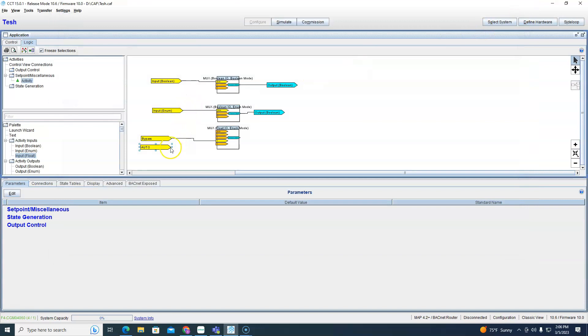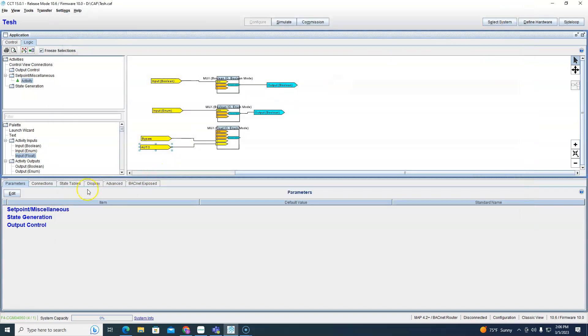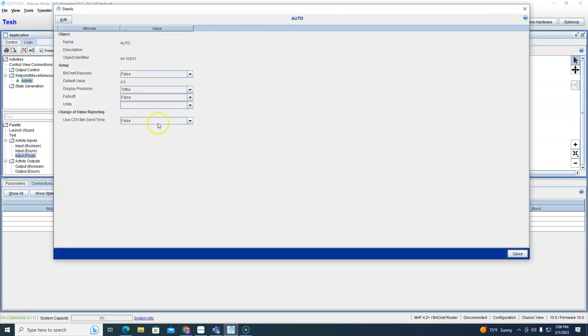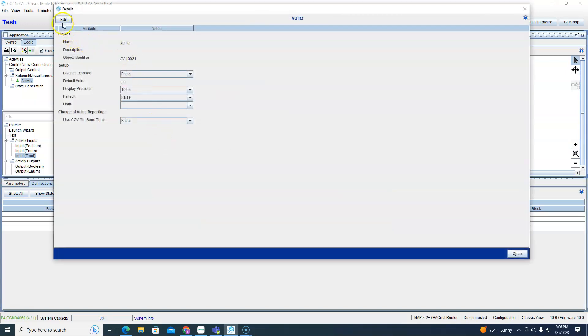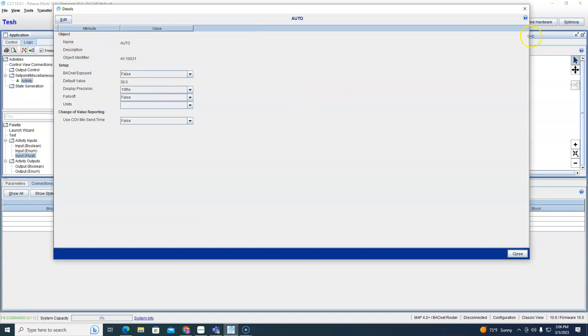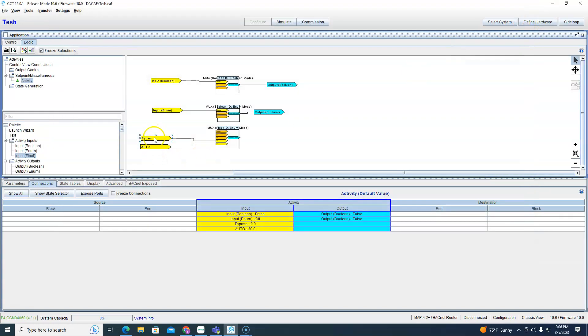And then this was auto. Four was auto, boom. So now that being a bypass block now I have connections. So if I had some other logic outside I could connect this and make it do something. For the time being I'm just going to put a 30 in here and I'll put a 50 in bypass.